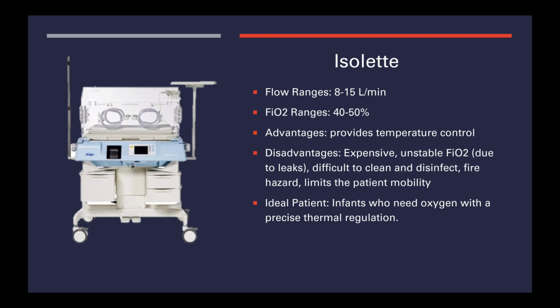The isolette has flow ranges of 8 to 15 liters per minute and FiO2 ranges of 40 to 50 percent. Advantages: provides temperature control. Disadvantages: expensive, FiO2 is unstable due to leaks, difficult to clean and disinfect, fire hazard, and limits the patient's mobility. The ideal patient is an infant needing oxygen with precise thermal regulation — mostly newborn or premature babies. Thank you for tuning in and watching — I hope this was very helpful for you.